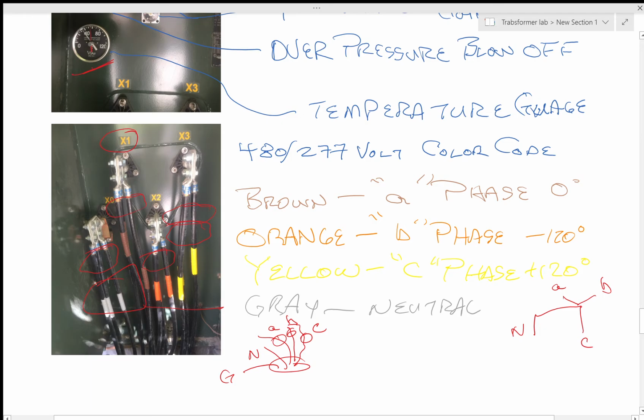You never run all the A phases in one conduit, never, ever. Or all the B phases in one conduit, or all the C phases in one conduit. The reason is that, once again, don't forget, these things are 120 degrees out of phase. So if I ran all the A phases in one conduit, I would have a huge magnetic field, and it would generate heat, and it would burn those cables up.